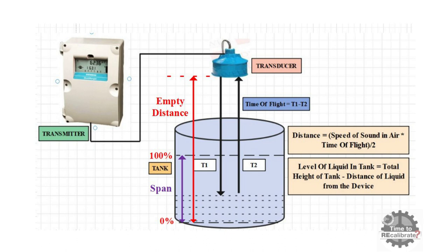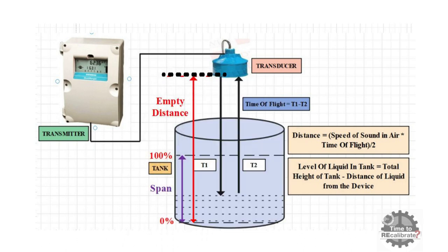First of all, let's start with empty distance. Empty distance can be defined as a distance from the sensor to the bottom of the tank or 0% level of tank. You have to have correct empty distance for ultrasonic level measurement.